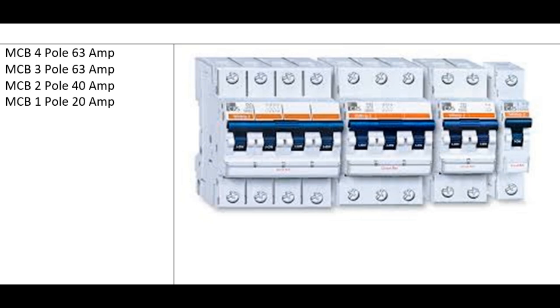Okay. Actually, an MCB is an automatically operated electrical switch. Miniature circuit breakers are intended to prevent damage to an electrical circuit as a result of excess current. They are designed to trip during overload or short circuit.